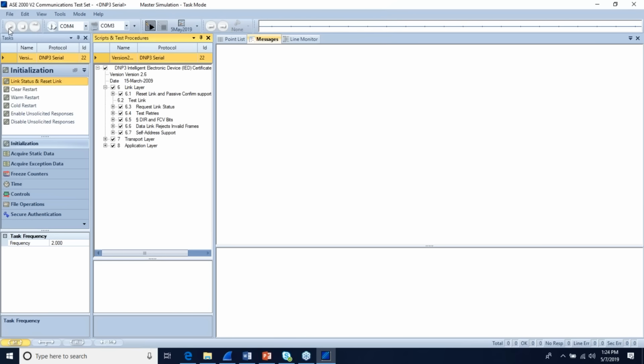And then based on my operators up here, I can actually commence that sequence and then view the responses from the device under test. And it saves the results. You basically take those results, export them, and then if you were going through official certification process with dnp3.org, it would review that. And there's some additional options available, such as getting your device listed as a conformant on their website, etc.